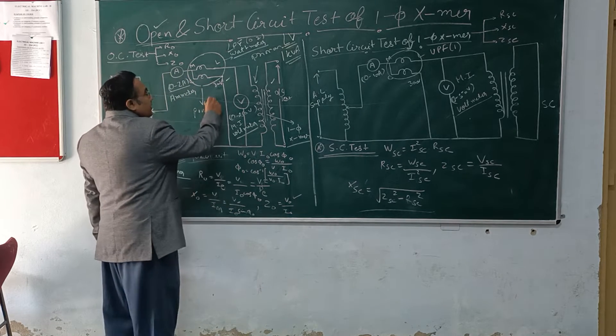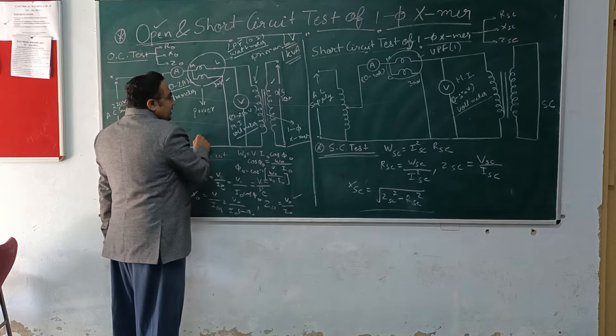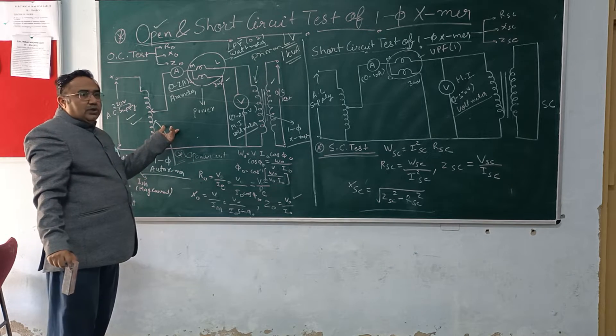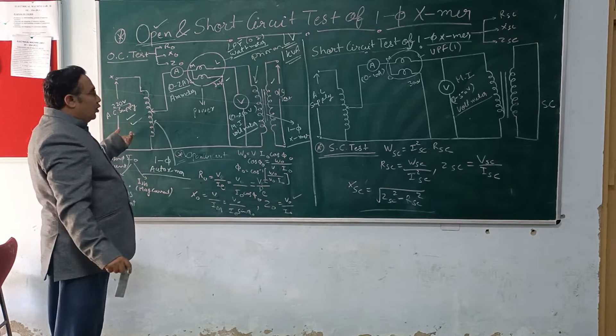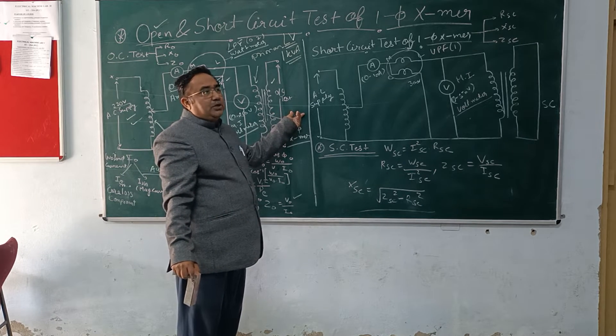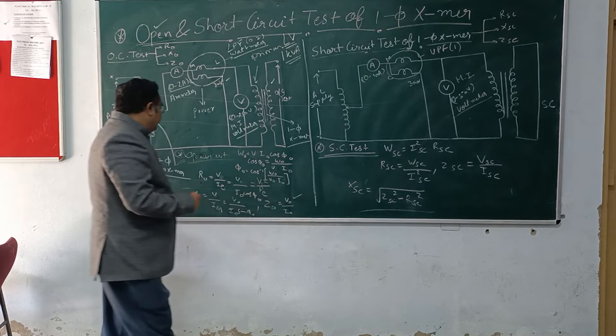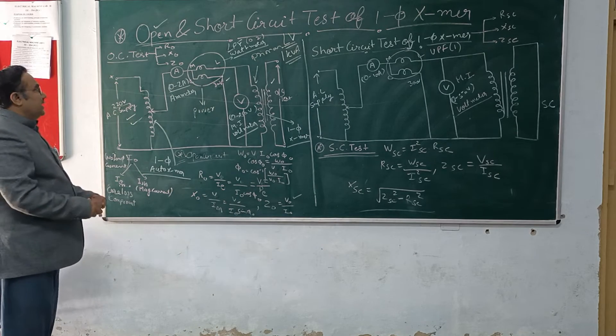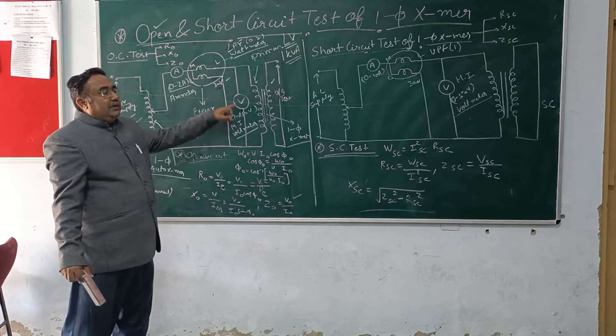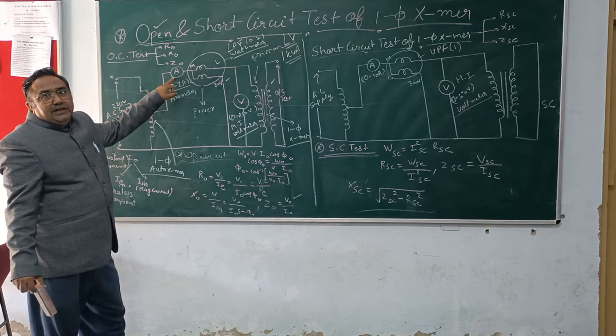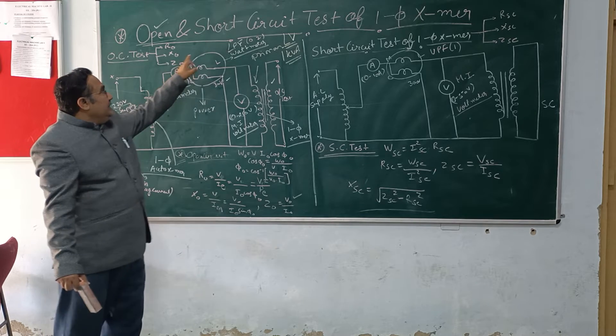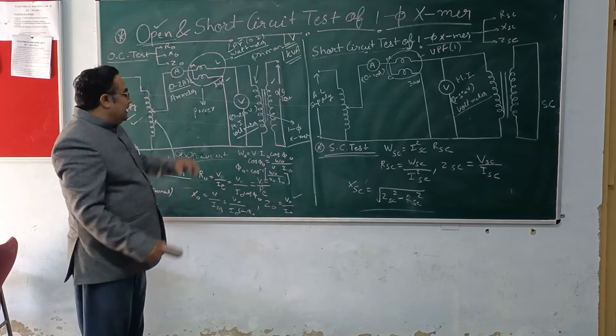Therefore, we always perform this open circuit test on the low voltage side. The low voltage side is being fed through a primary source - through autotransformer - and the high voltage side, or the secondary side, is kept open. Now we will take some readings. We will take the rated voltage reading with the help of this voltmeter - how much current flows when rated voltage is applied to the primary winding, that we will know from the ammeter, and the wattmeter will give us the power reading.